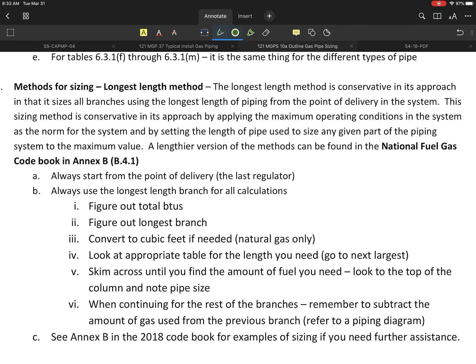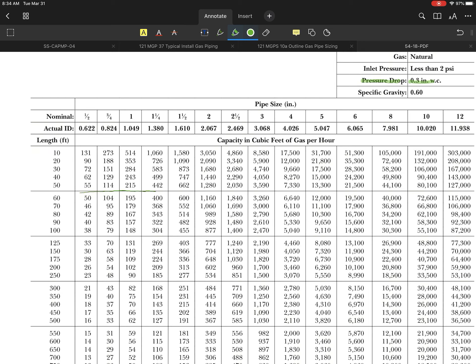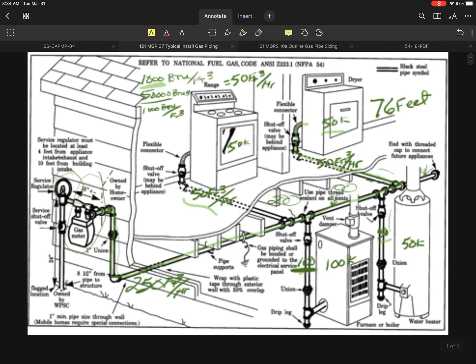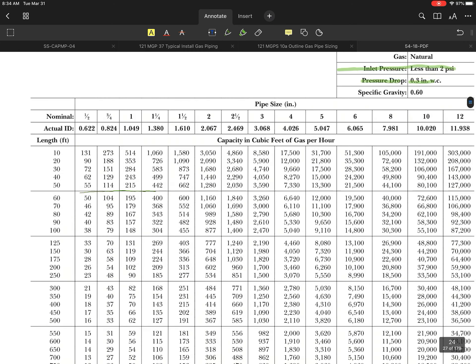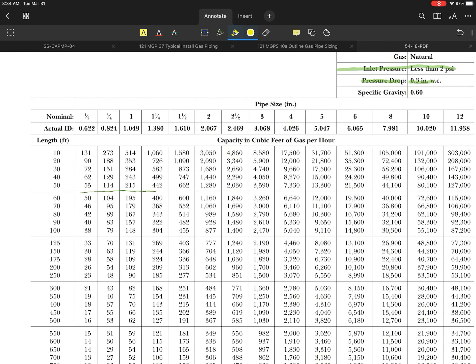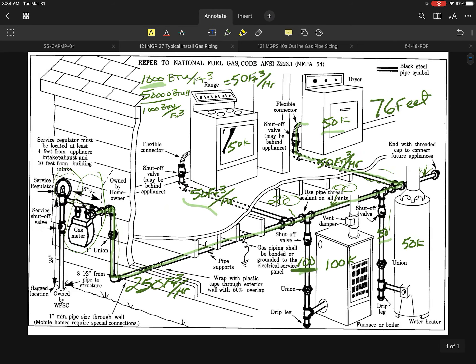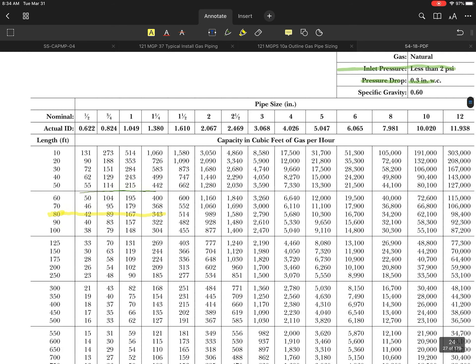Let's go to the code book. In this example, I chose a pressure drop of 0.3. My inlet pressure is a normal 7 inch, so that fits into that category. I had identified that we were at 76 feet. Since there's no 76, the first one that I have to use in this example is going to be the 80 foot row. That means I'm going to use that single row for my entire system.